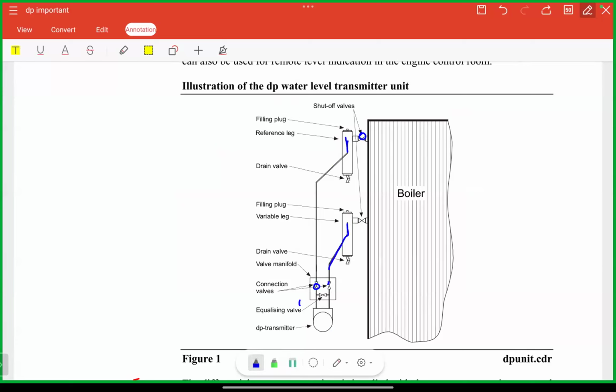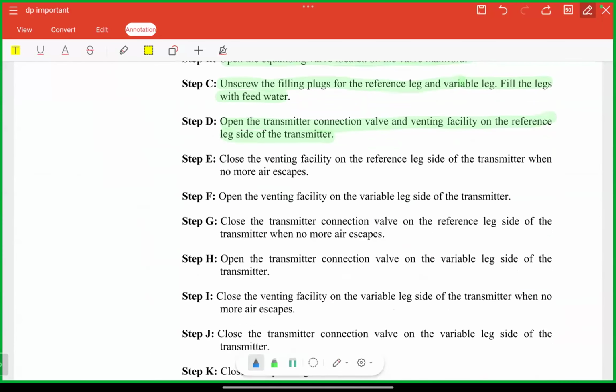this variable leg and the reference leg are both provided with a slope. At least 5 degrees of slope is required. What is the purpose of this slope? To remove the air. The slope positively ensures air can be displaced and vented out from the vent plug. Initially, you keep your vent plugs open. Understood? So open the transmitter connection valve and venting facility on the reference leg side of the transmitter and vent out all the air. After the air is vented out, close the venting facility on the reference leg of the transmitter when no more air escapes. Open the venting facility on the variable leg of the transmitter and close the transmitter connection valve on the reference leg side when there is no more air.